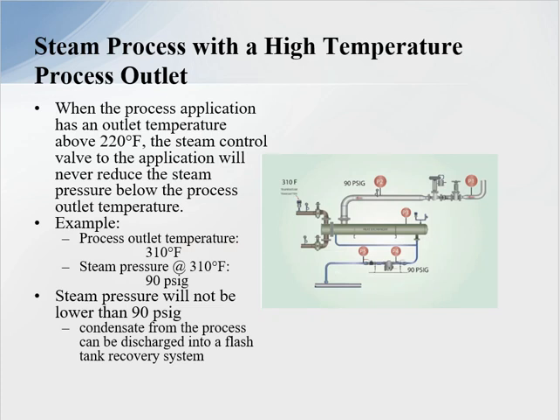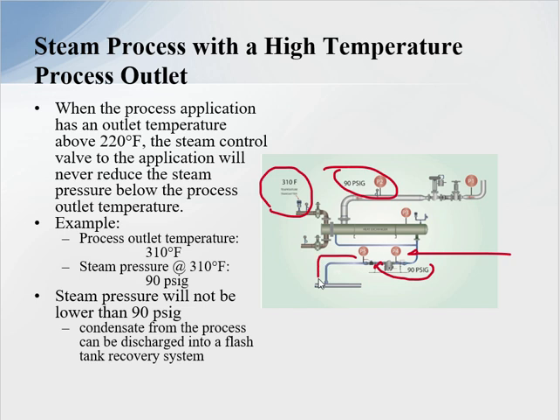The next application is steam processes with a high temperature process outlet. In this example, the process outlet is 310 degrees Fahrenheit. At 310°F, referencing the steam tables, that corresponds to 90 PSI. So the lowest pressure at the drain device at P4 is going to be 90 PSI. Therefore, I have enough differential to discharge into a pressurized return system and go into a flash tank — this is a high temperature process outlet where I can recover flash steam and send it into a lower pressure system or cascade it.